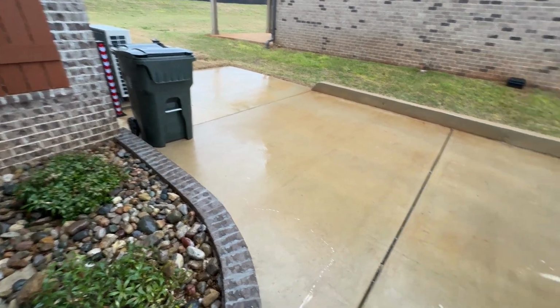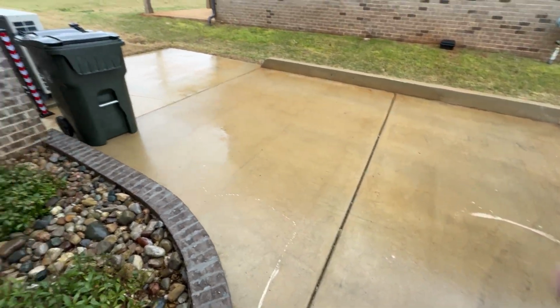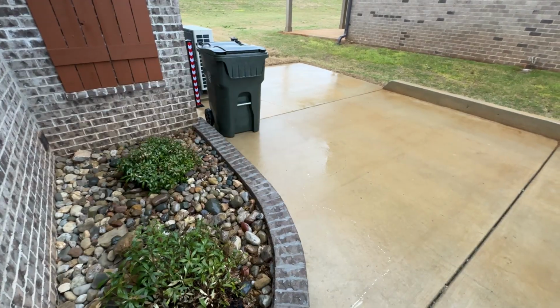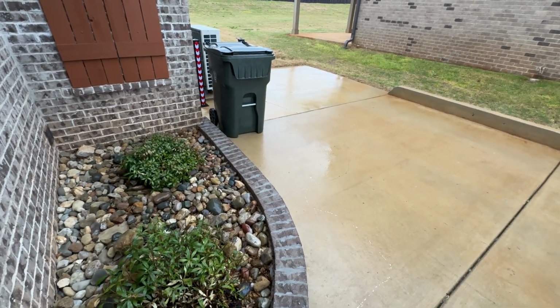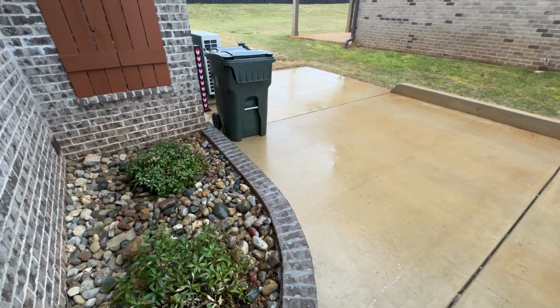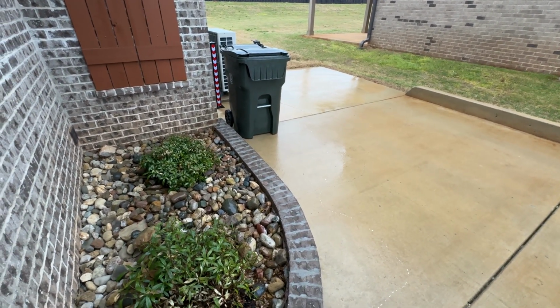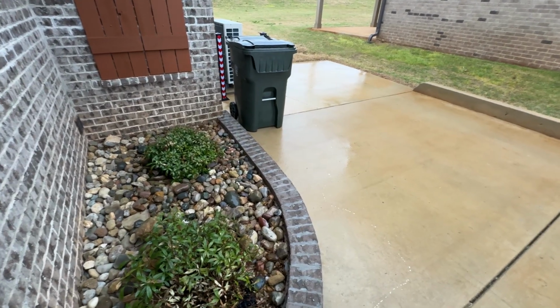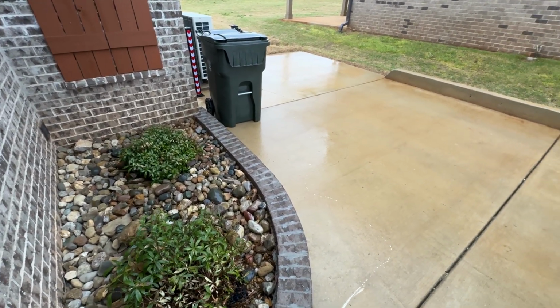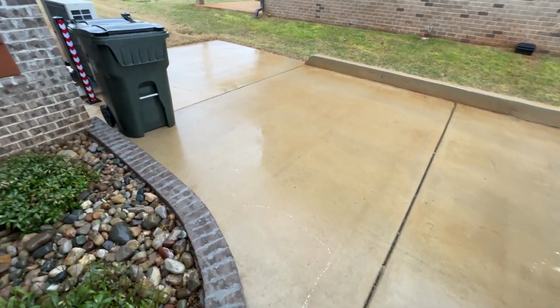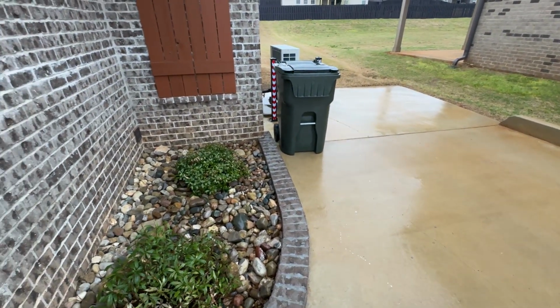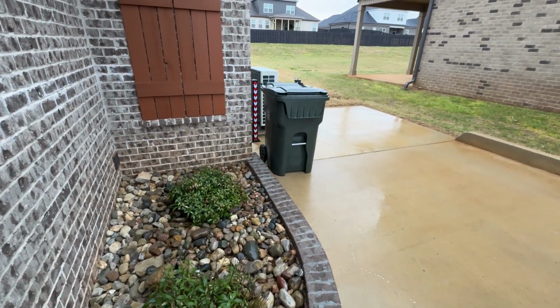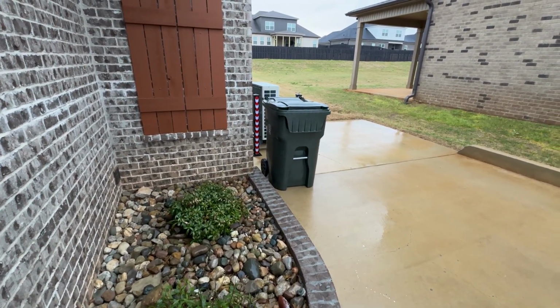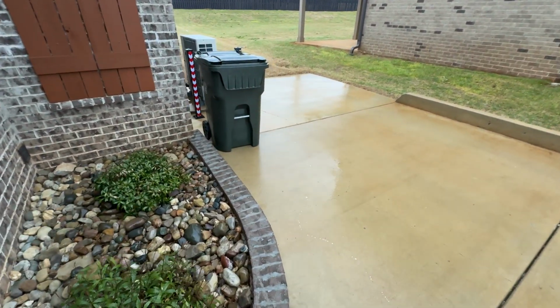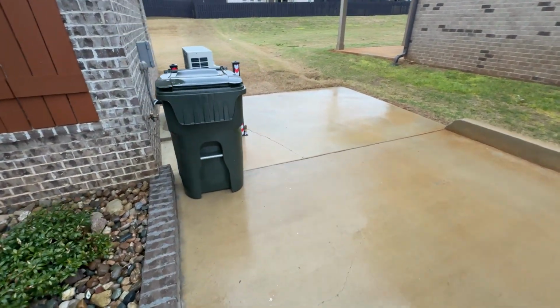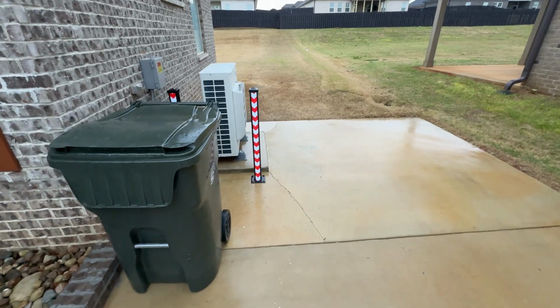They witnessed the power surge, and then they went 4 houses up my street and looked at the other transformer boxes and found high voltage at 4 other houses. So now it was confirmed by their own crew that we have high voltage in this community. And as a result, they called a substation guy out, because they don't have adjustable taps in these boxes where you can turn the voltage down at the transformer on the street. Obviously, we have all underground utilities in this community. So it has to be done at the substation.